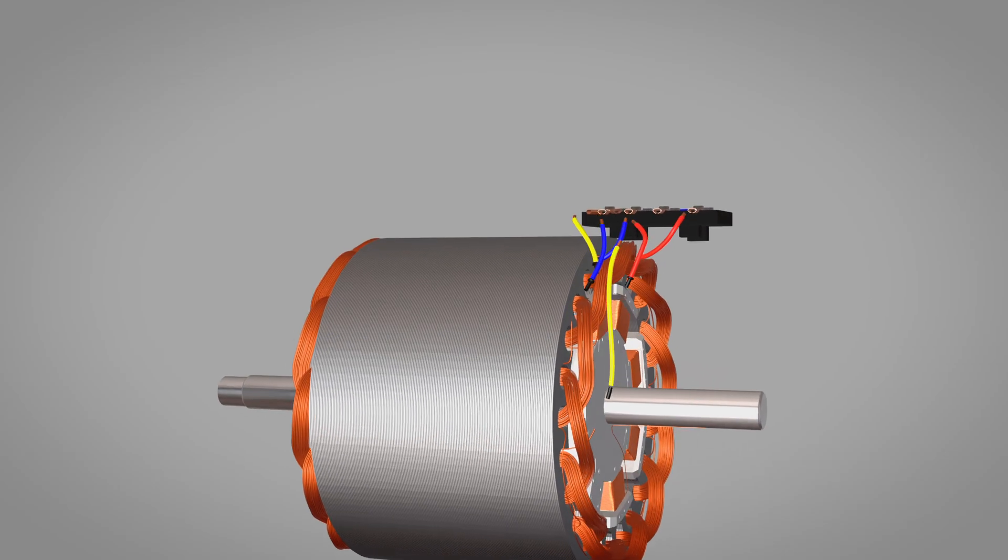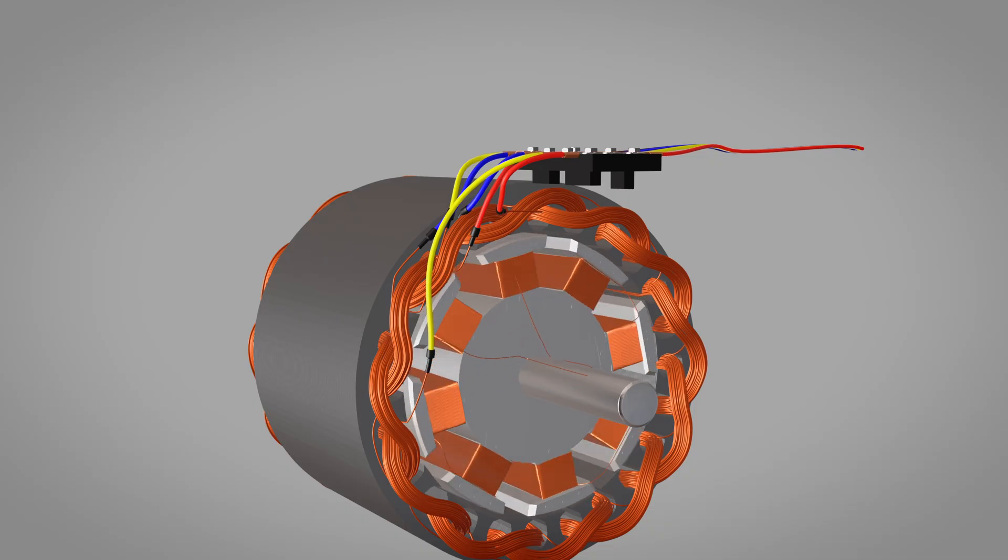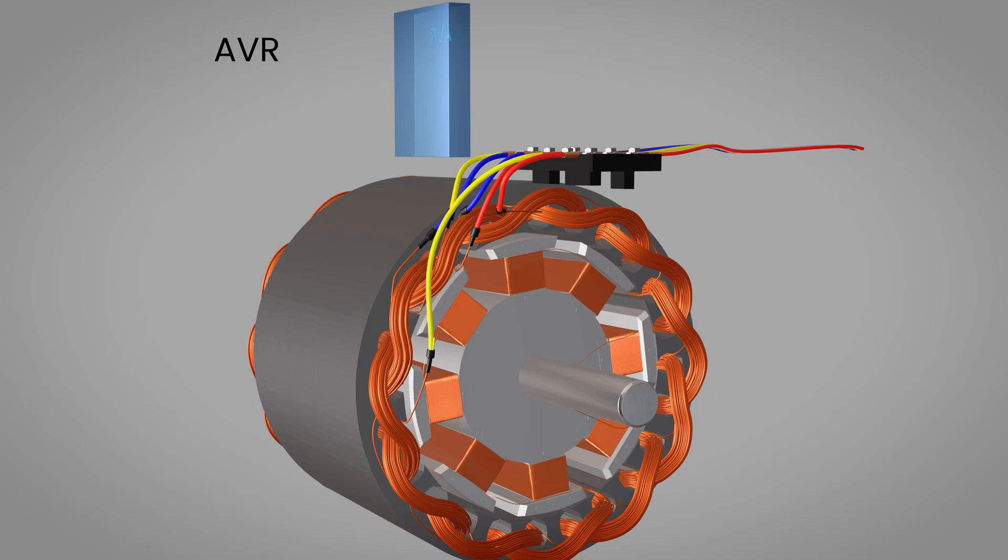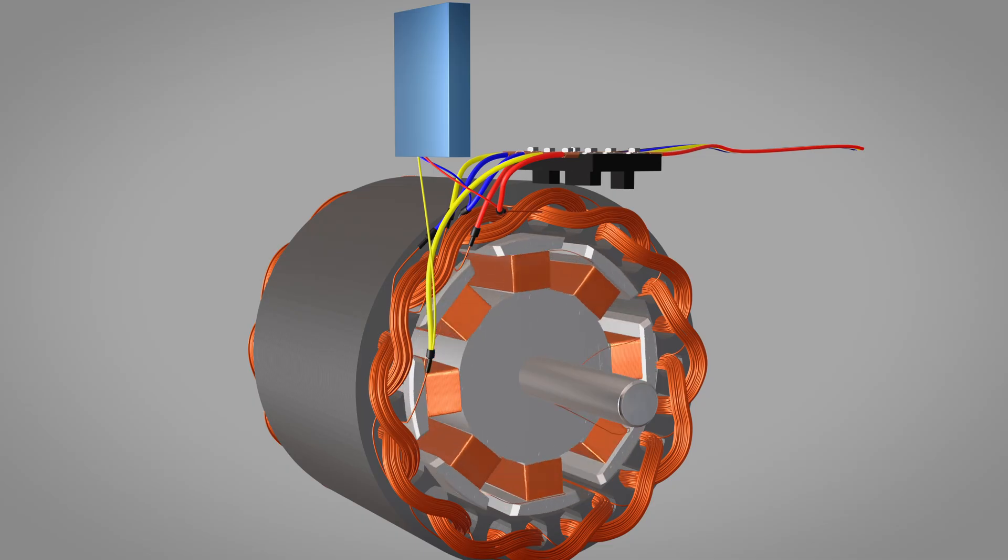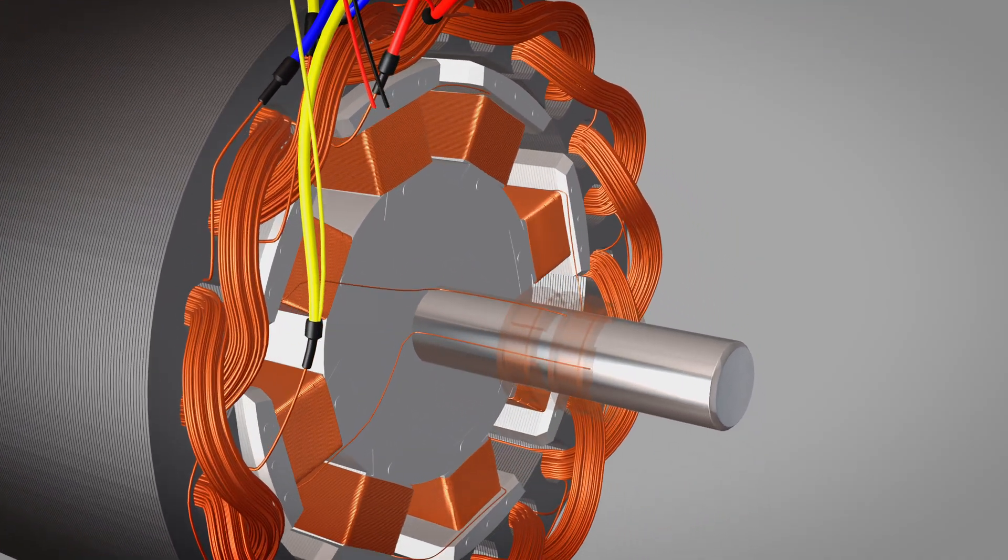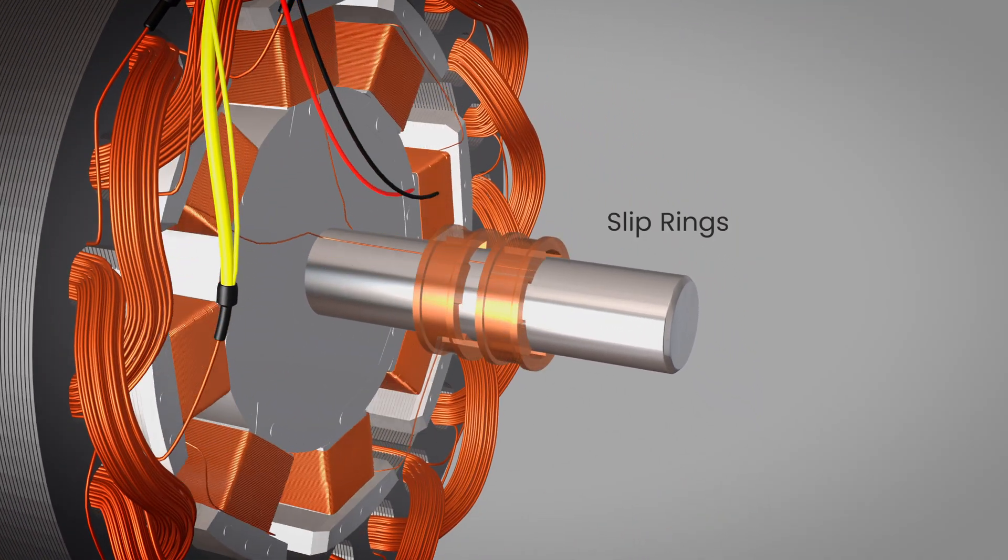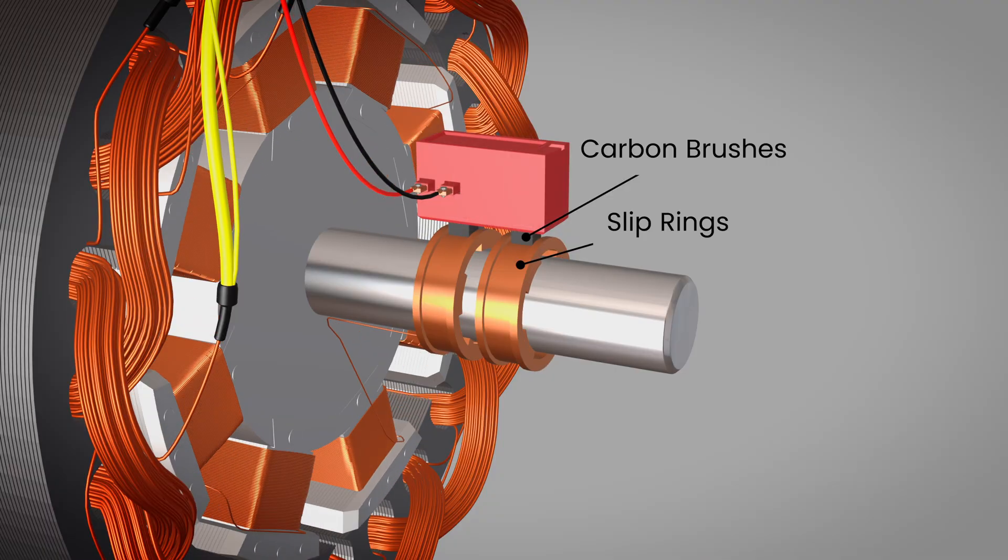Our alternator is known as shunt self-excited because it generates its own field current for field coils without requiring any external DC source. At the heart of this system lies the automatic voltage regulator, AVR, which connects to the main output terminals and continuously monitors the generated voltage. Inside the AVR, rectifier diodes convert the stator's AC voltage into steady DC current, which is essential for creating stable magnetic poles in the rotor field windings. The converted DC current travels to the rotating rotor windings via slip rings, conductive rings mounted on the shaft, and carbon brushes that maintain constant contact with those rings as they spin.